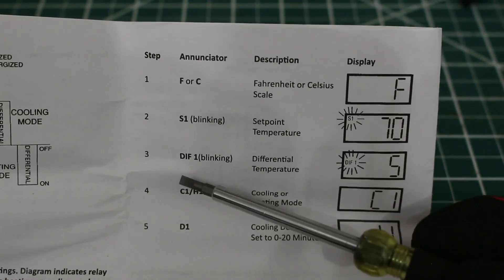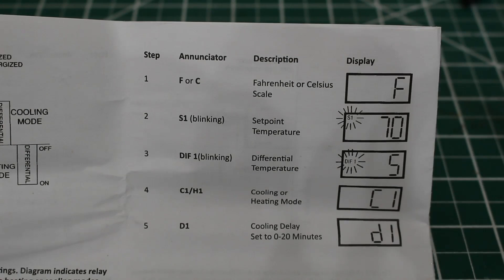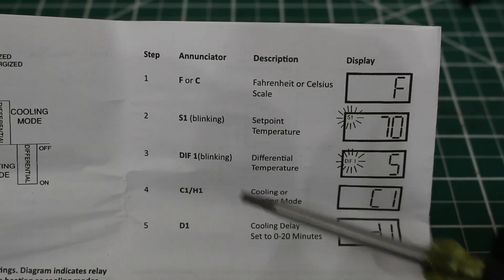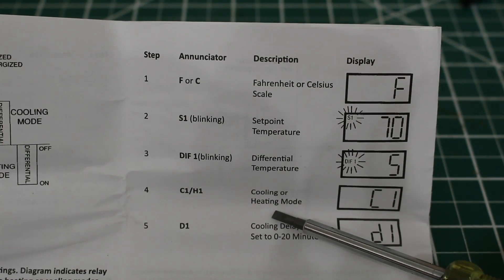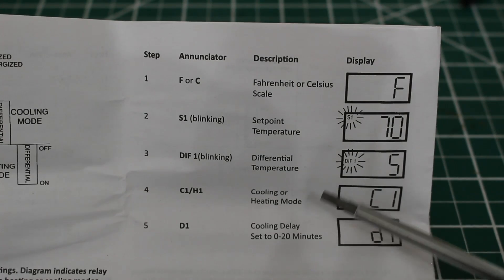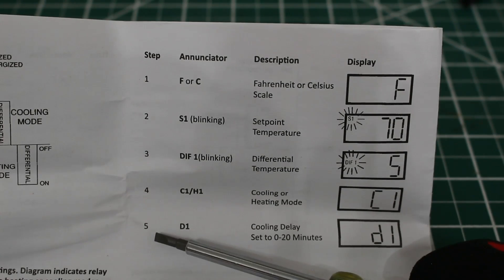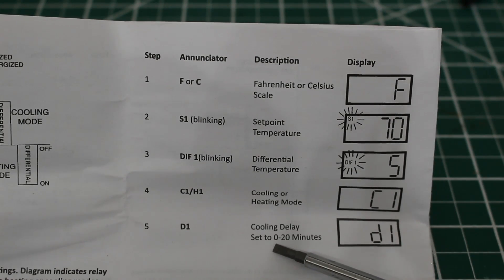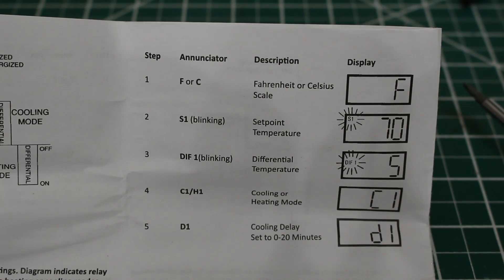Click Set and you're done with that. This is a universal control, so you could use it for a cooling or heating application. That brings us to step four — you're going to see C1 or H1. C1 stands for cooling and H1 stands for heating. Click Set on your desired application — cooling will be for refrigeration and air conditioning. Then step five is D1, which is your cooling delay. You can arrange it from zero to 20 minutes. I'd recommend zero or three minutes max.